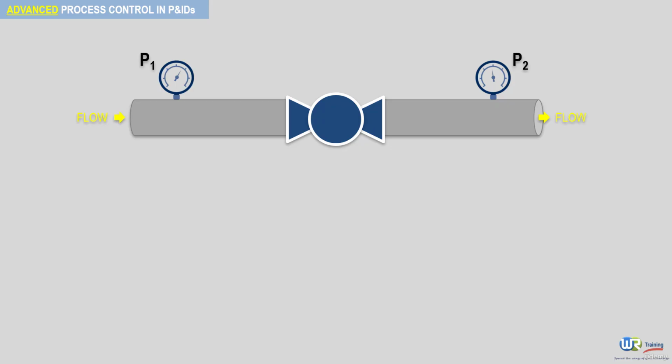When the valve starts to close, it generates more pressure drop. This causes extra pressure drop along the route, making the route less attractive for flow, so the flow rate decreases too. This means that by partially closing a control valve, the pressure on the downstream side of the control valve is decreased, and the flow of the pipe will be lower as well.